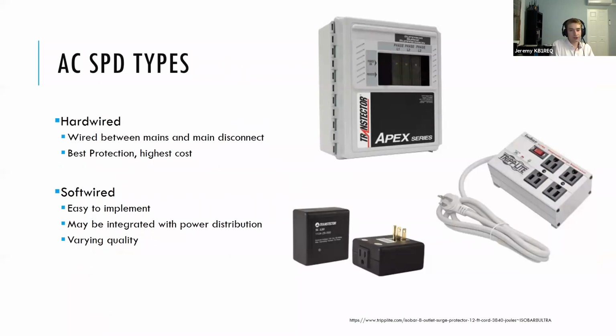As I mentioned, and as we saw in that previous picture, you've got hardwired SPDs, you've got soft-wired SPDs. Hardwired ones are designed to wire into your distribution panel, so they are installed by an electrician, but once they're installed, they protect all the circuits off that distribution panel. Best level of protection. A very good alternative to that is soft-wired, and there's a wide range of them, and they're very easy to implement. This is good because in some situations you can't specify the electrical design.